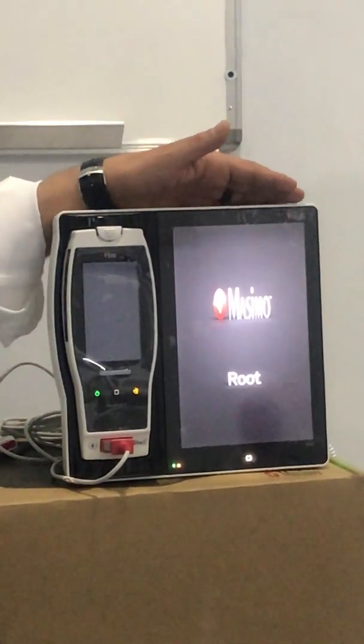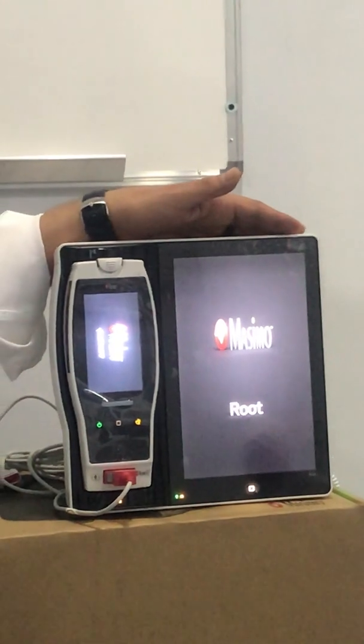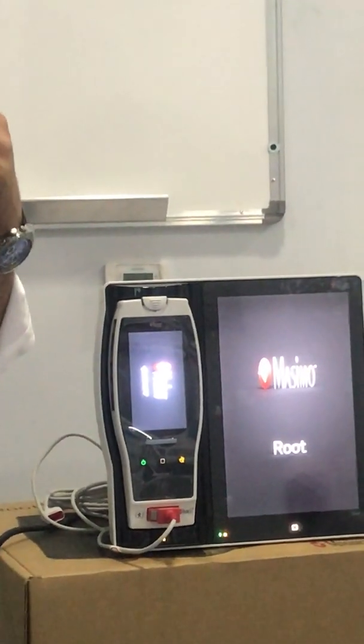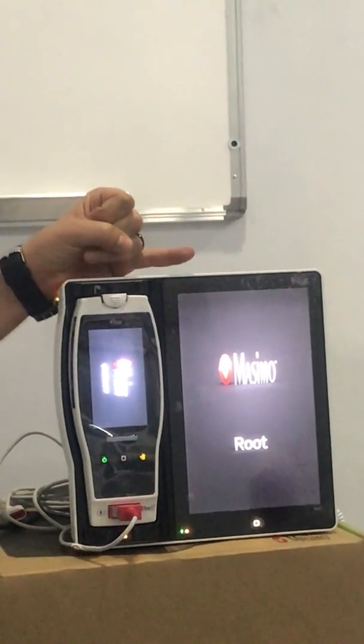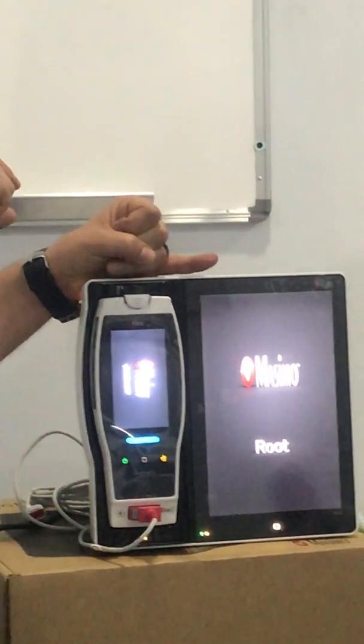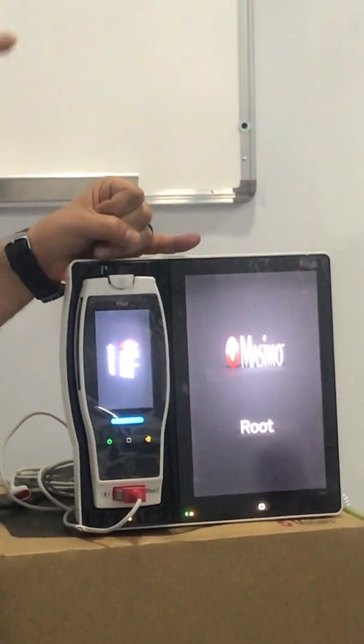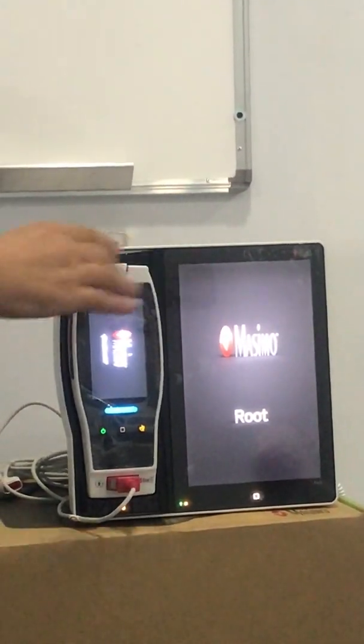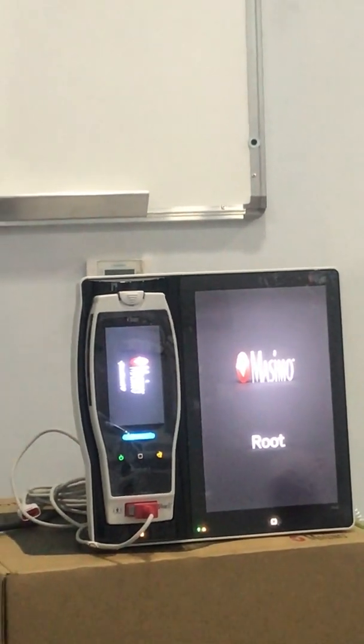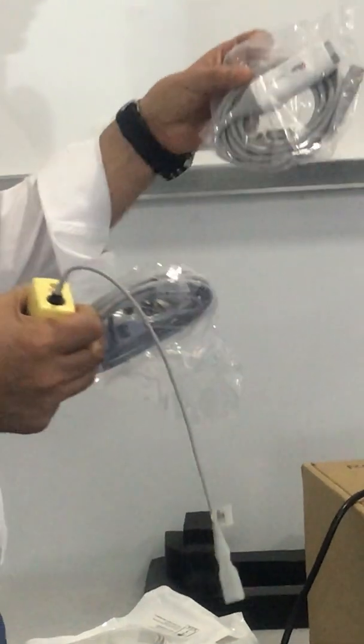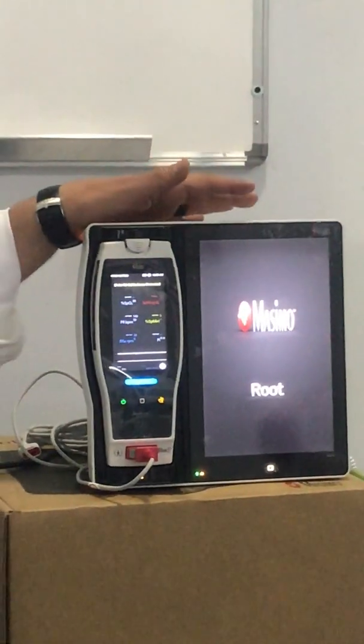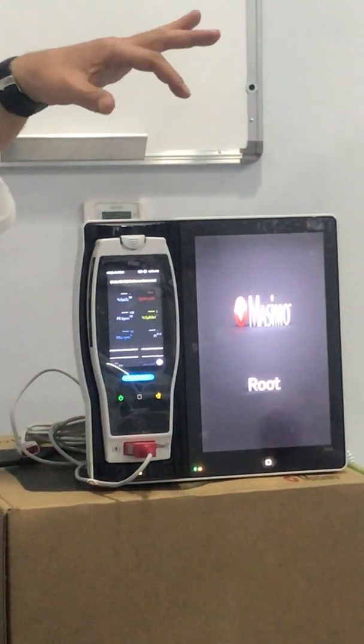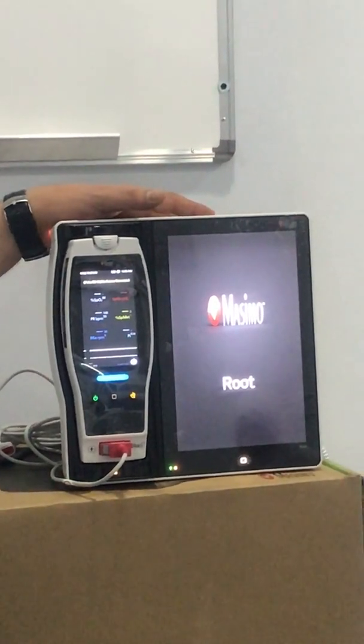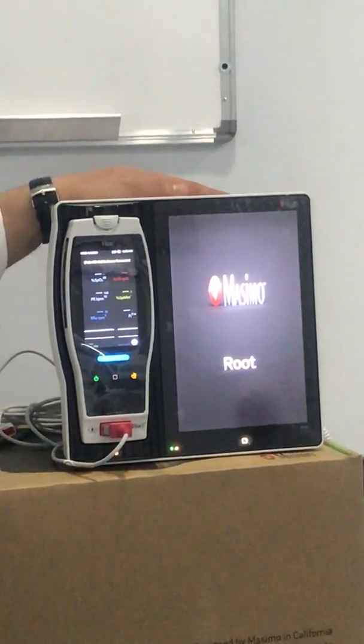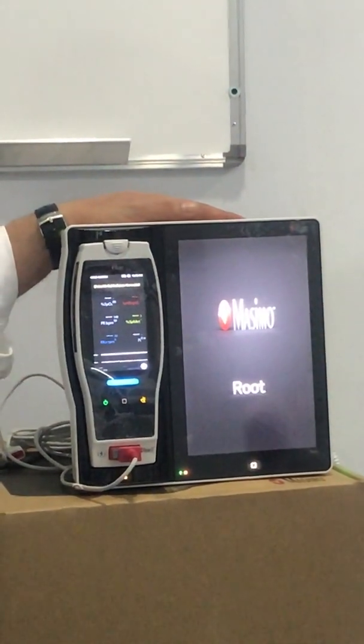But generally, in order to measure any parameter, you will need 4 main things. A sensor on the patient to capture the signal, and a cable to transfer the signal. A module to translate the signal. Here is a module, here is a module, here is a module also, and here is the 4th one. Okay? So, a module to translate the signal and a screen to display. And according to the type of module, there is a type of sensor. Each module has its own sensor.